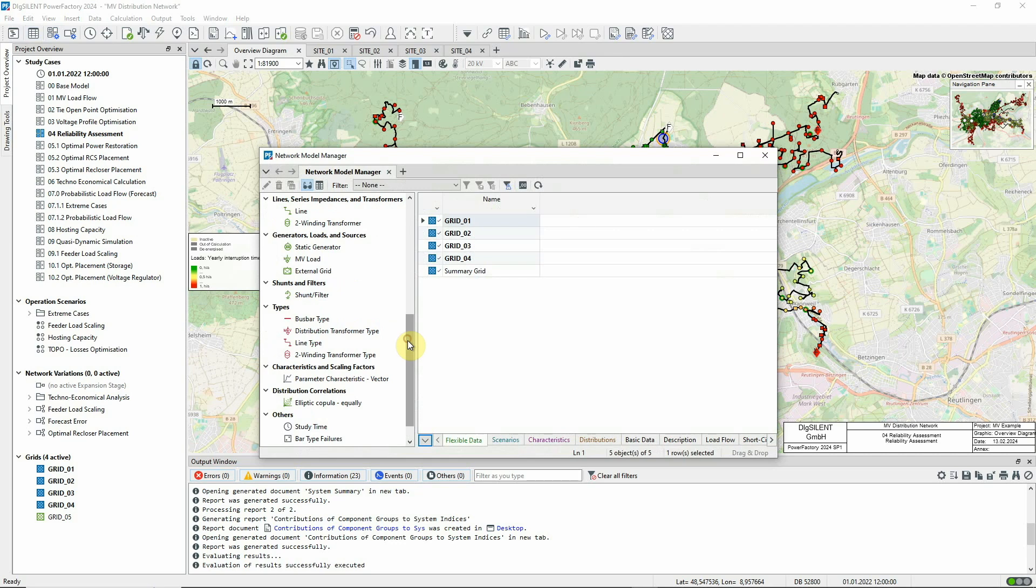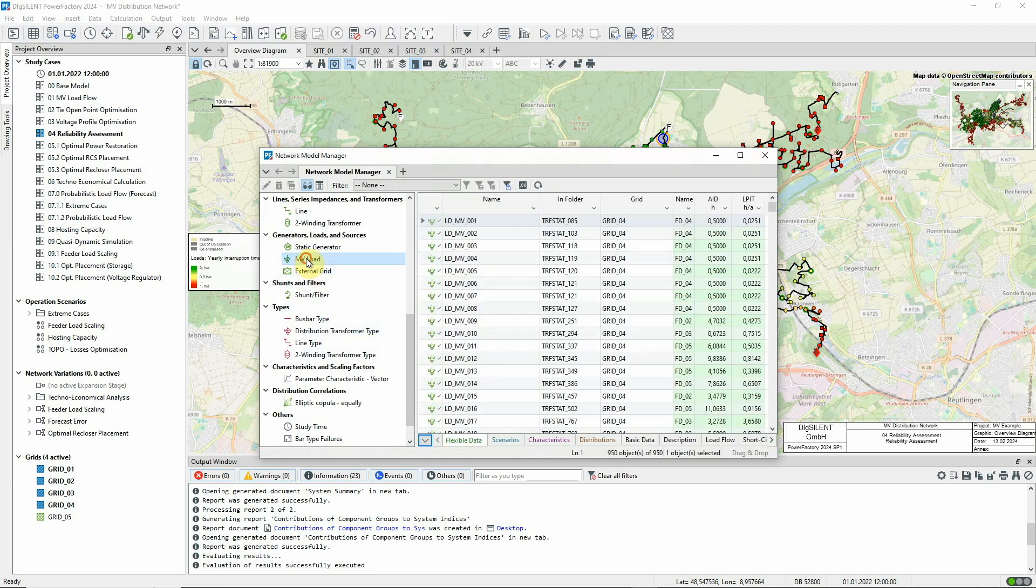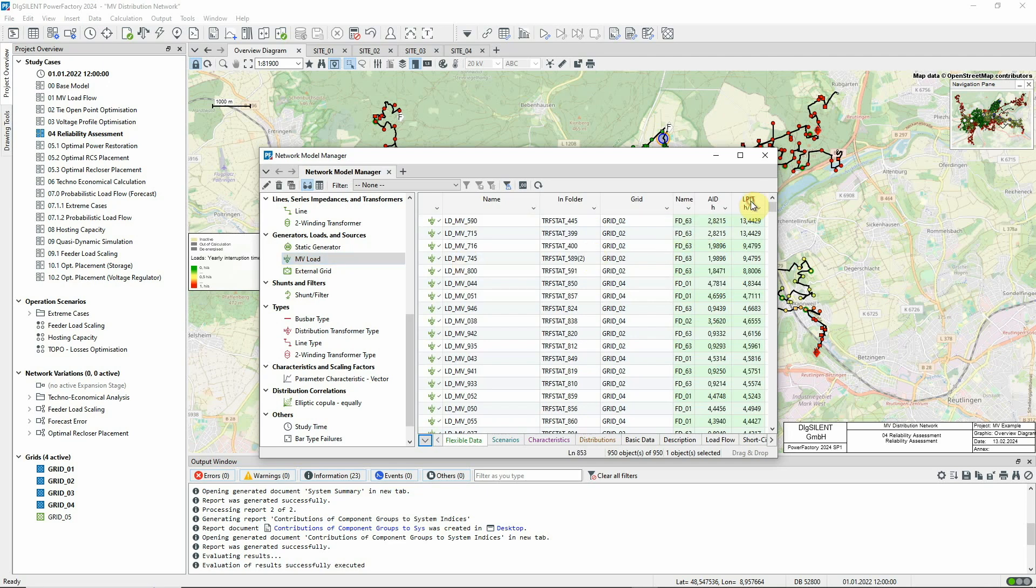Let's look at the calculation results for the load objects and see which loads suffer the most interruption to supply in terms of time. We'll use the result variable load point interruption time as our criterion. Load LDMV590 is at the top of the list. Let's see where this is in the network.